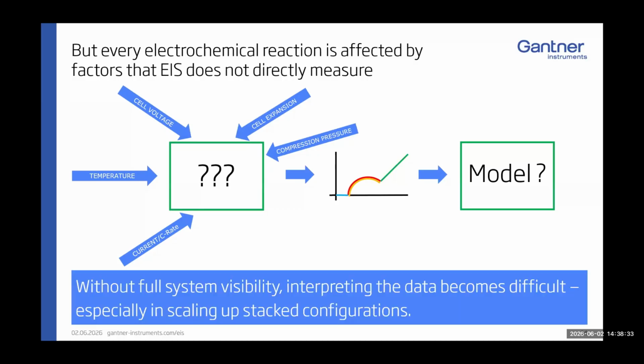EIS plus time series data gives you full system visibility. Just one measurement alone is not everything. You cannot just use an infrared camera and say you're watching for thermal runaway. You also need current and voltage measurements, and if you have EIS on top, you can detect changes very fast.